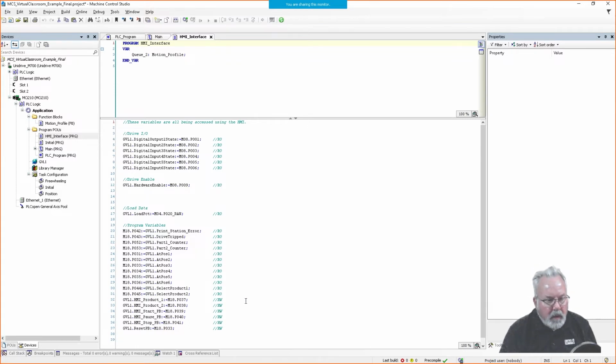Now, my HMI would be talking Modbus TCP IP. Okay, so what you don't see as part of this program is that in the HMI program, you need to assign Modbus register addresses to all of these menus and parameters that you want to have access to. There is another video on my YouTube channel in which I tell you how to do that, how to assign Modbus register addresses to drive parameters. So that's the interface there.